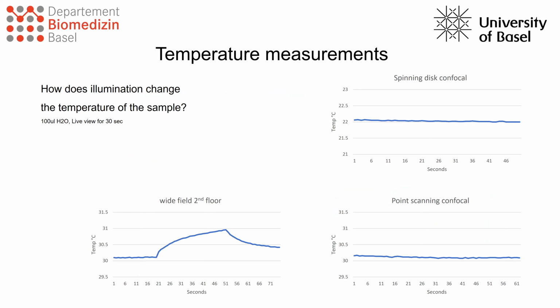So then finally we looked at illumination, or if light actually has an influence on the temperature of the sample. We used water in a reservoir. I mean, this was used as an easy to use sample, but it's of course not a real sample. And we know that a real sample might have a different light absorption, so could have a different behavior. But we just used water as an easy-to-go liquid. We illuminated the whole thing in a live view for 30 seconds with the full power light that the system, or whatever system we measured, delivered.